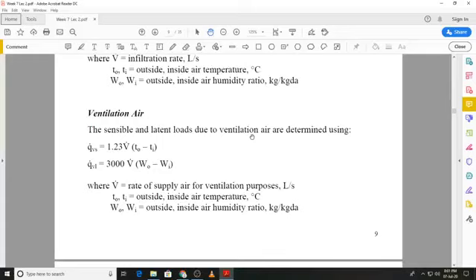And finally, ventilation. Ventilation is again calculated by using the same equations that we have for calculating the load due to infiltration. This time, however, the volume flow rate due to ventilation will be different, and that volume flow rate will depend on the type of activity inside the conditioned space and other factors inside the conditioned space. Usually these values are given to us in tables, or they will be given to us directly, that for example the ventilation requirement is so much, and we will use those. Otherwise there are tables that you can refer to, and a simple table is given, I think, in our book as well, and if required we will use that table to calculate the amount of ventilation air.